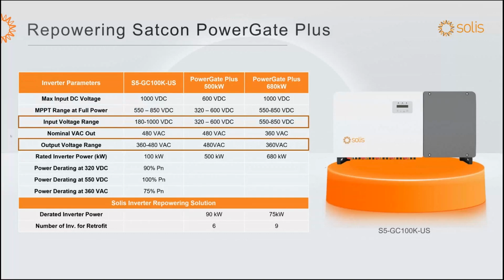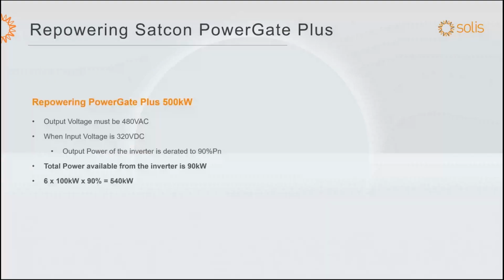At the bottom here, we show it will require 6 inverters, 100 kilowatt, to replace the 500 kilowatt inverter, and 9 to replace the 680 kilowatt inverter. The inverter will be derated to 90 kilowatt for the 500 kilowatt and to 75 kilowatt for the 680. The way the derating is done: for the output voltage of 480 volt, there is no derating required. But for the low input voltage range of 320 volt, the inverter will be derated to 90%. That's why the 100 kilowatt will be derated to 90 kilowatt. Therefore, to replace a 500 kilowatt inverter, we will need 6 of those inverters.